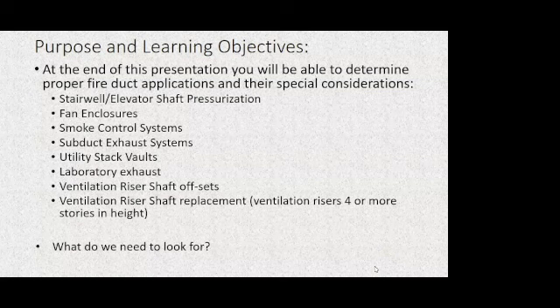Utility stack vaults, if you're dealing with high-rise buildings, very, very tall structures where they're going to start taking advantage of utility grade voltage to keep the electrical conductors smaller, we're going to talk about the trade-offs that happen in terms of fire resistance up within the building, and those trigger ventilation requirements that may exceed the 2-hour threshold. That is a very, very important threshold when it comes to fire resistance for HVAC systems.